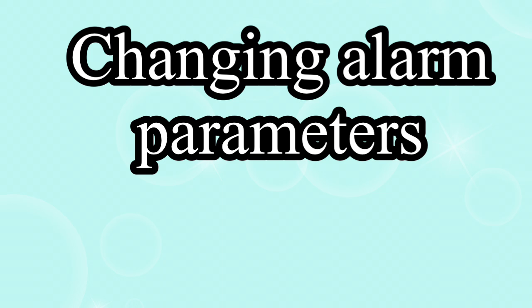When the dose is first entered, it can take a few minutes before the sensors stabilise, and during this period the machine may alarm, as the machine is temporarily outside the alarm limits. As you only have 5 minutes before the machine enters failsafe mode, it's better to widen the parameters for this period. You can then tighten them if you want when the sensors have stabilised.